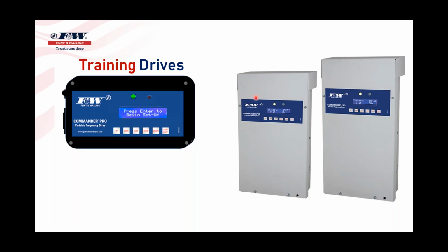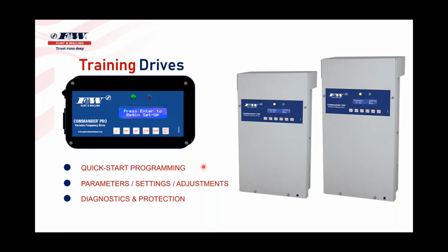And I do a little drive training class, but I had these little things made up over here, which is essentially the programming of the drive itself. I can ship dozens of these things out. So when we do a contractor meeting, everyone in the class can program drives with these little trainer drives. It'll walk you through that quick start. If these are something you're interested in, let us or one of your Flint and Walling guys know. You can see what kind of parameters, settings, and adjustments, all the diagnostics and the protection and the fault log and the activity there is all part of that as well.